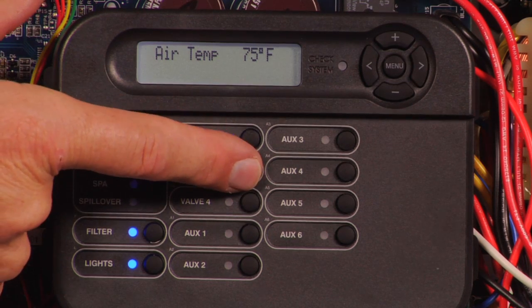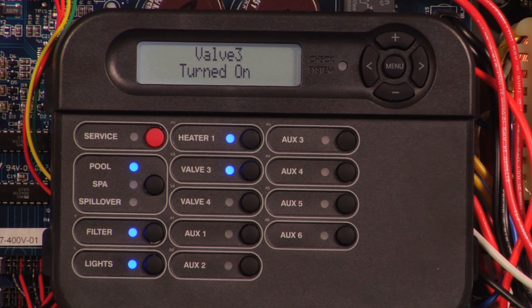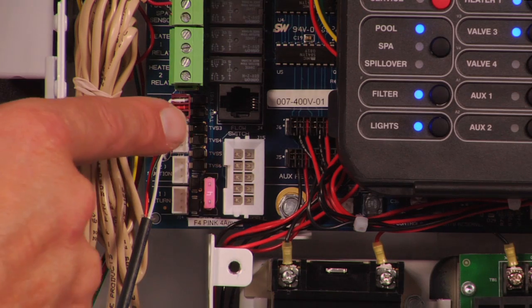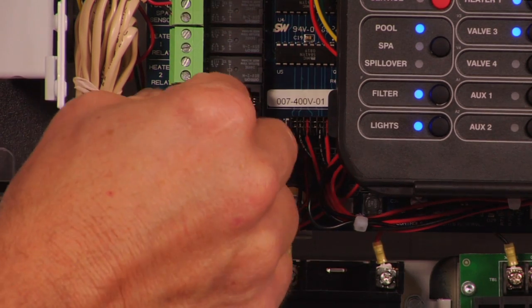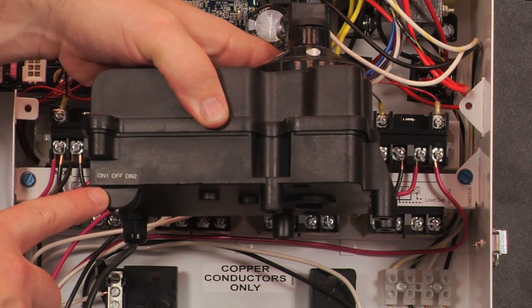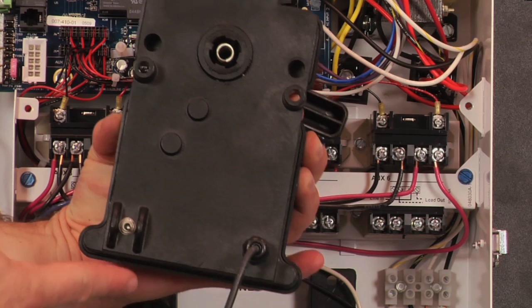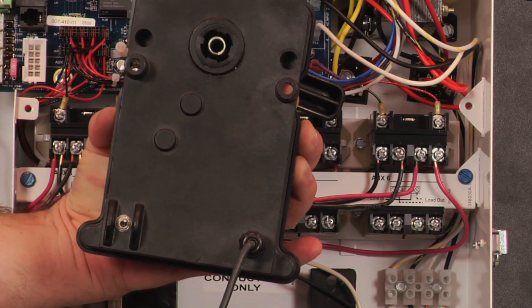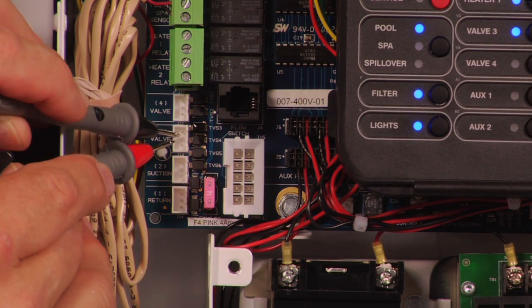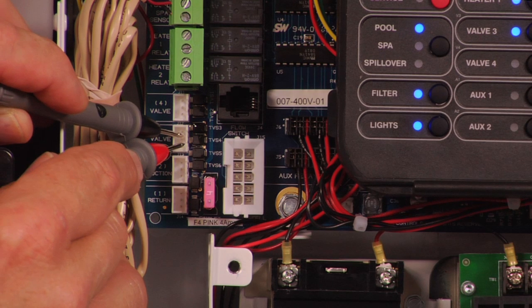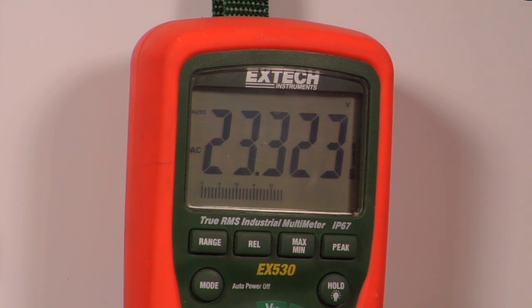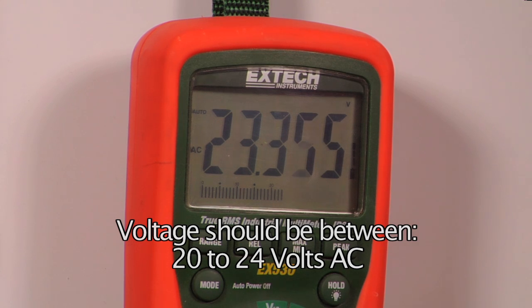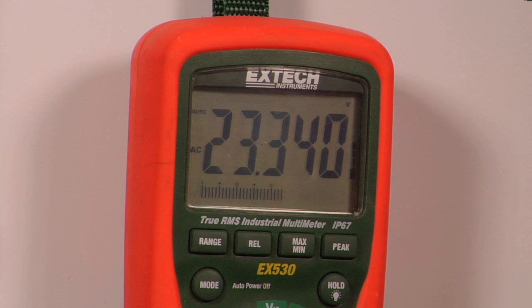If a valve actuator does not turn when the corresponding valve button is pushed, there may be a problem with the ProLogic or the valve actuator. Verify that the actuator connector is plugged into the correct connection. Verify that the actuator toggle switch is not in the off position. Unplug the actuator connector from the main board. Measure the voltage on the actuator connector pins on the main board. If the actuator is turned on, the reading between the lower pin and the center pin should be 20 to 24 volts AC. If there is no voltage reading, the main board is bad and needs to be replaced. If there is a voltage reading, the valve actuator is bad and needs to be replaced.